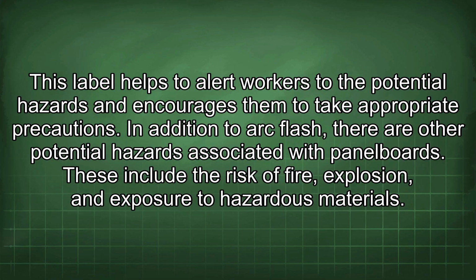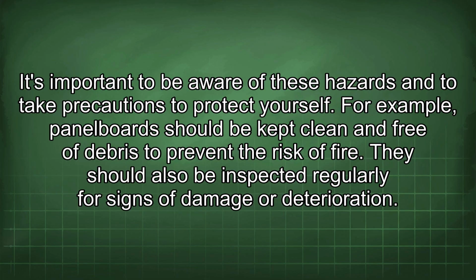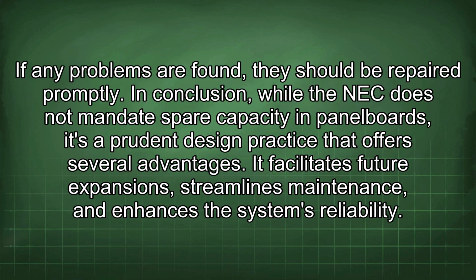In addition to arc flash, there are other potential hazards associated with panel boards. These include the risk of fire, explosion, and exposure to hazardous materials. It's important to be aware of these hazards and to take precautions to protect yourself. For example, panel boards should be kept clean and free of debris to prevent the risk of fire. They should also be inspected regularly for signs of damage or deterioration. If any problems are found, they should be repaired promptly.